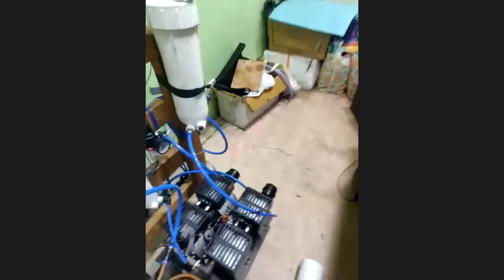What are your input pressure and sieve tank pressures? Input pressure fluctuates between 2 to 3 bar, and at the sieve, the maximum air pressure goes up to 2.5 bar. I think you need to increase that, at least up to 3 bar. You can try increasing it up to 3 bar. Even for lithium zeolite? I heard that for lithium zeolite, we don't need that much pressure. Actually, with lithium we're not going that high, just about 1.5 bar. So 2.5 bar is pretty good.